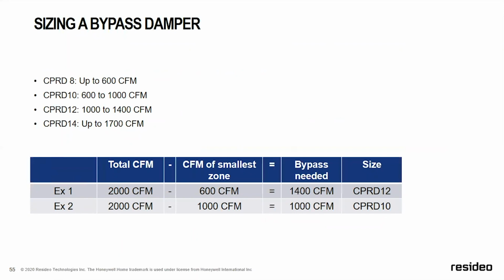So when you look at these CFM ratings, this is not typical of standard ductwork. And I can explain that in an easy way. We are dealing with smaller duct, typically you're going to have 2 elbows and a 5-foot piece of ductwork. So you're going to be running at a higher static level, which means if you go to a duct chart or a ductilator, you're not going to see 8-inch get up to 600 CFM. But if you increase the static level, you will see it. So an 8-inch can do 600 CFM, 10-inch is 600 to 1,000, 12-inch is 1,000 to 1,400, and the CPRD 14 is up to 1,700 CFM.